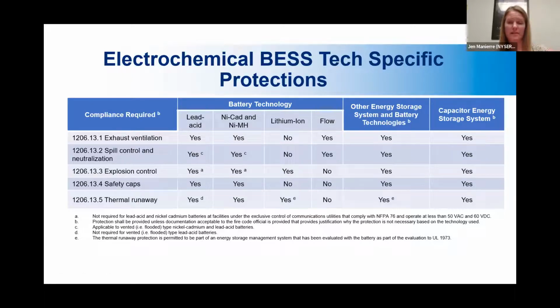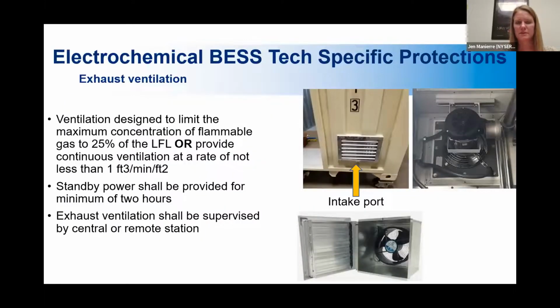We're not going to go through every component of this because it's not fire code training, but I like to show folks snippets of what's in there. A little more detail on the exhaust ventilation. Like I've mentioned before, when that requirement is triggered, it's designed to limit the concentration of flammable gas to 25% of the lower flammability limit, or they can meet that obligation by just having a certain rate of continuous ventilation all the time. And if there's an exhaust ventilation system, it needs to have its own standby power for up to 2 hours. In case something goes wrong, you can at least still keep ventilating it.